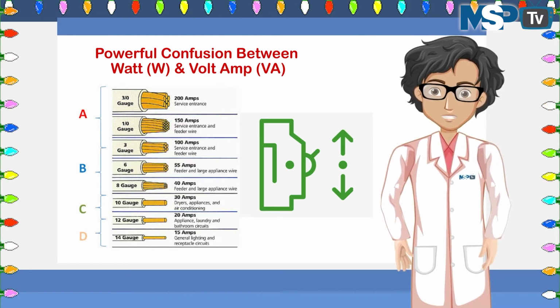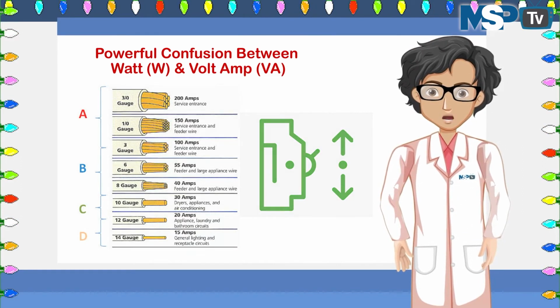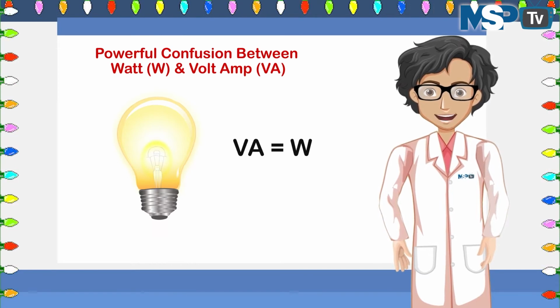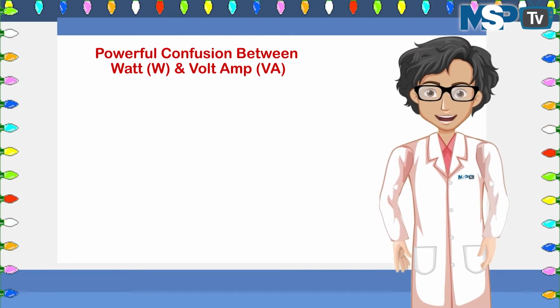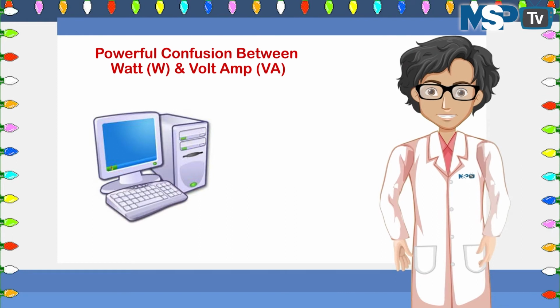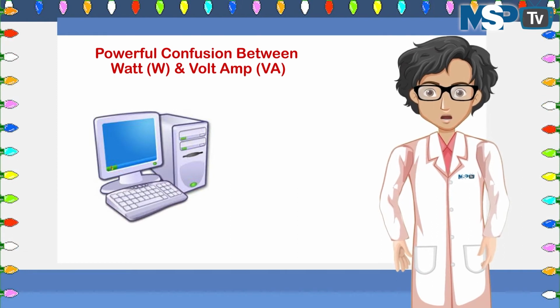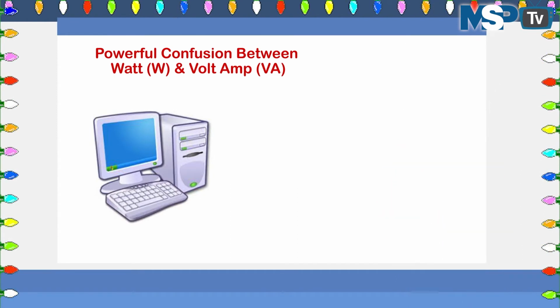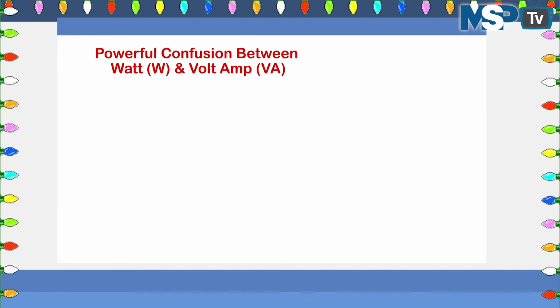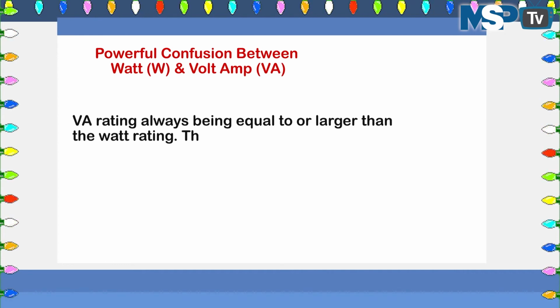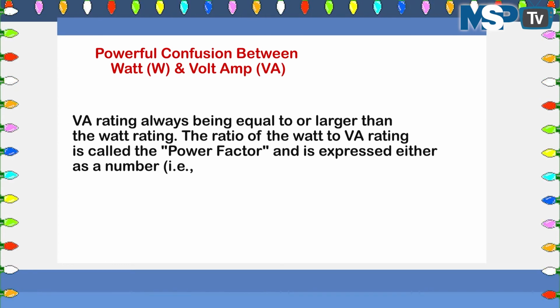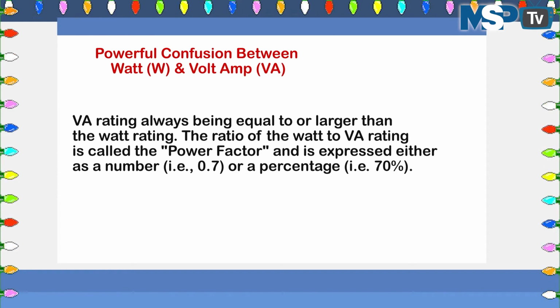The VA and watt rating for some types of electrical loads, like an incandescent light bulb, are identical. However, for computer equipment, the watt and VA ratings can differ significantly, with the VA rating always equal to or larger than the watt rating. The ratio of watt to VA rating is called the power factor and is expressed either as a number, like 0.7, or as a percentage, that is 70%.